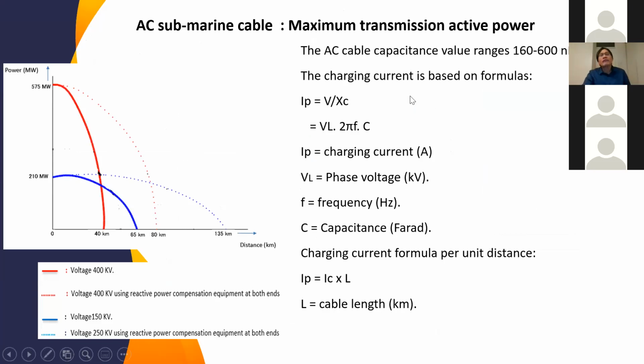For AC, we have a limitation here. AC cable, AC submarine cable, has a big capacitance value here. The longer the cable, the more capacitance produced. At the end, we will produce only reactive power and the active power becomes 0. From this formula, we can see the longer the cable, the more reactive power produced. This is a typical curve for AC submarine cable.